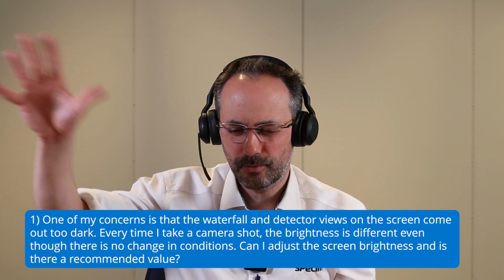Also, you can see on the right-hand side of LumoScan or Lumo Recorder, you have what we call image correction, and check if it is enabled or disabled. And then if it is enabled, it might be the dark reference is not valid anymore and the white is not valid anymore and things like this. But yes, as I say, right-click, and then you can change the contrast and the brightness.